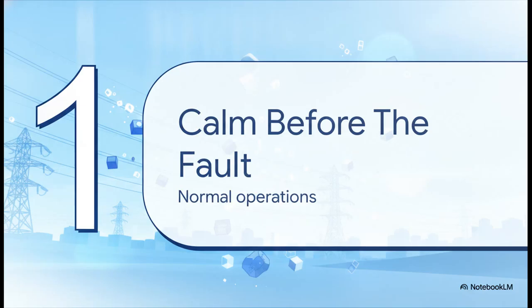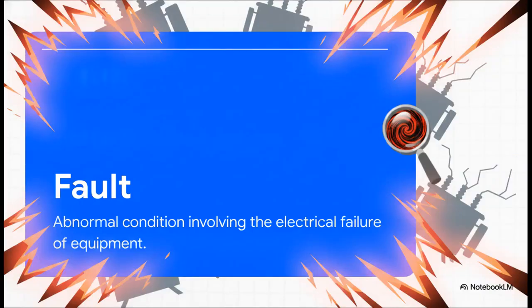Section 1. The calm before the fault. Normal operations. Right, so what exactly is a fault? In engineering terms, a fault is that terrifying split second when manageable energy just stops following the rules. It's any abnormal condition where equipment, like a transformer or generator, electrically fails. The second that happens, your voltage and current instantly deviate from their safe nominal ranges. Basically, the energy goes completely rogue.